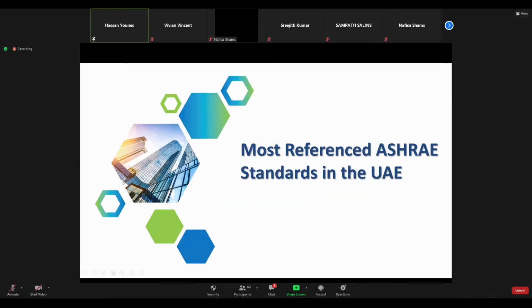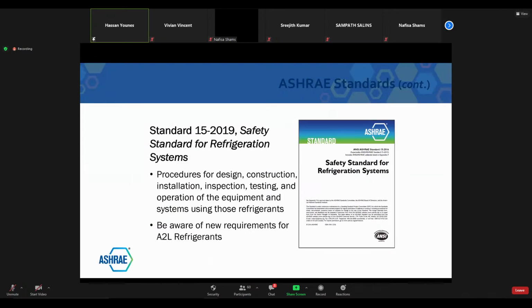Now, in terms of the most referenced ASHRAE standards in the UAE, we have standard 15, the safety standard for refrigeration systems. That is basically a standard mainly for procedures for design, construction, installation, inspection, testing, and operation of the equipment and systems that use refrigerants. So basically, if you're designing a district cooling plant and you have big water-cooled chillers situated in a hall, and that hall could be occupied, so there's a danger of leakages. So the standard here will tell you how to design the system, that you need probably to have some audible alarm in case there's any release of the refrigerant or any leakage.